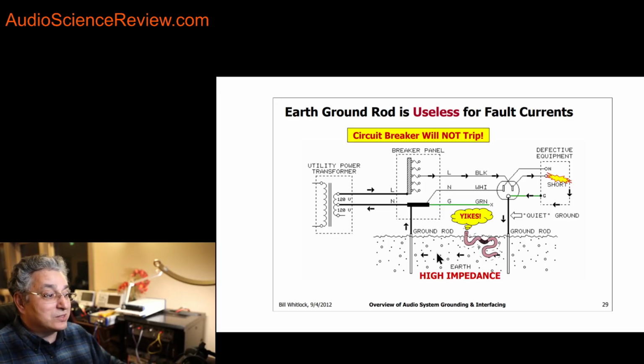And because this impedance is high, a lot of that current can get lost in here, dissipated in here. The power can be dissipated in here. So as a result, what carries through this path now can be low enough current that this breaker will not trip. It will not see necessarily 15 or 20 amps to break. It'll stay conducting. And if that stays conducting, it means the energized chassis of your equipment that's now at 120 volts continues to be at 120 volts. You touch that, you can die.